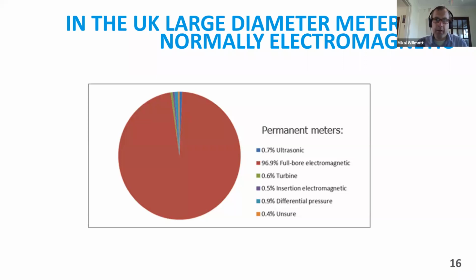job. Now, the maturity of the water industry is different in the UK, and that is no longer acceptable, and rightly so. We're a customer-focused business, and we've got to find ways of doing what we need to do while making water always available. It's not acceptable to turn off the water now. And so clamp-on ultrasonics have become very popular because you can put them onto pipes. You don't have to turn the water off. You don't have to divert the water. You don't have to come up with expensive contingency plans. So for the remainder of my presentation, on my slides, we'll primarily look at electromagnetic meters and clamp-on ultrasonic meters.